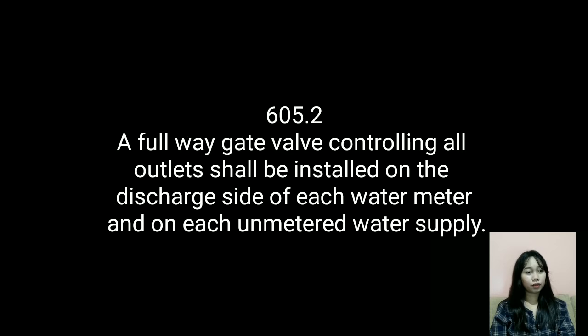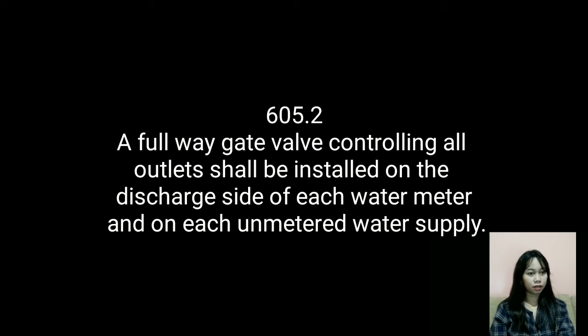In Section 605.2, a full-way gate valve controlling all outlets shall be installed on the discharge side of each water meter and on each unmetered water supply. Water supply piping supplying more than one building in any premise shall be equipped with a separate full-way gate valve to each building, so arranged that the water supply can be turned on or off to any individual or separate building. However, the supply piping to a single-family residence and its accessory building may be controlled by one gate valve.